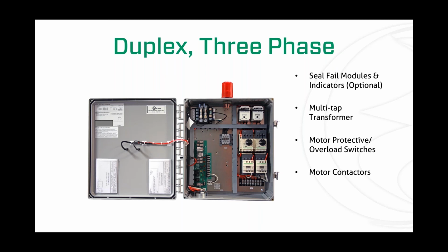This is a three-phase panel, so this particular panel has that multi-tap transformer in it. We need to make sure that we tap it correctly. It's going to make this panel much more versatile for use with varying three-phase voltages.